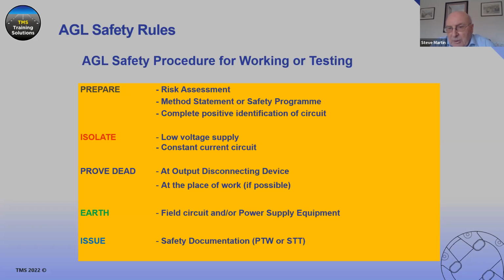Prove dead the output disconnecting device, and if possible at the place of work. That's usually difficult if it's in the field, but if it's inside in the AGL switch room substation, then that is possible, and we'd always want to put a tester on before we put our hands on anything.